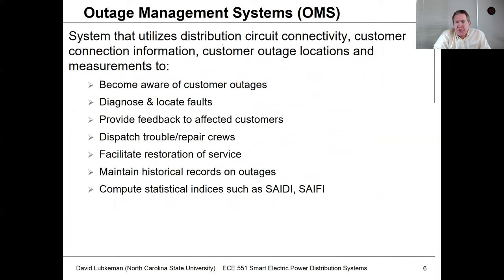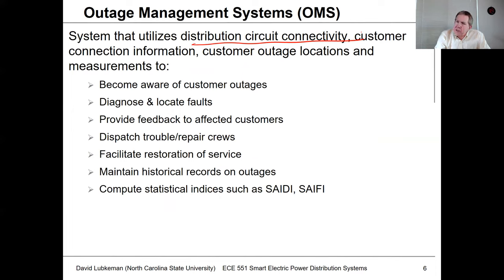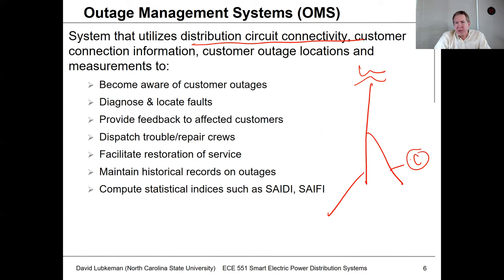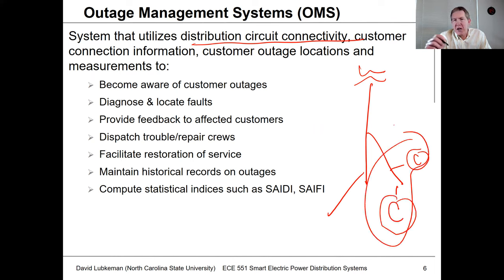The outage management system focuses on how you actually restore customers that are out of service due to something like a fault. The type of information needed includes distribution circuit connectivity — essentially the same information that goes into a power flow. You need to know how a customer interconnects all the way to the substation, what's between the substation and that individual customer, what phase they're connected to, and the common upstream customers to help find the nearest upstream protection device.